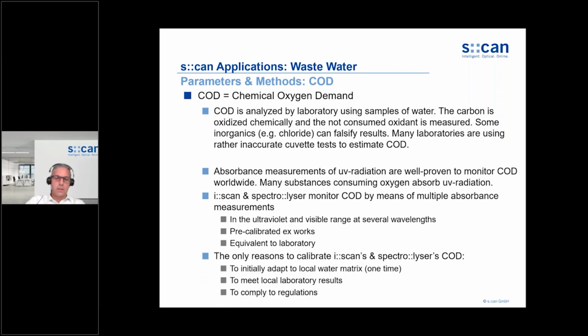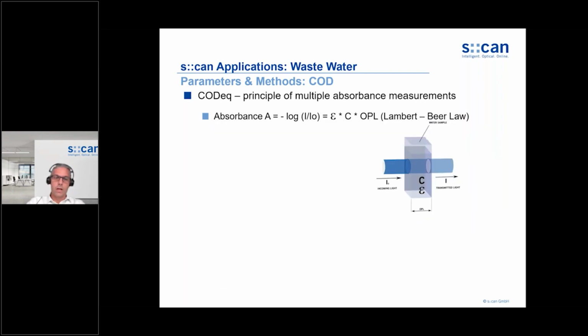There are a few reasons to calibrate the COD of the iScan and the spectro::lyzers. Aging is not a reason to calibrate it on a periodical basis. The reason is to initially adapt to the local water matrix. This is done one time during installation to match the results of the local lab and to comply with regulations.